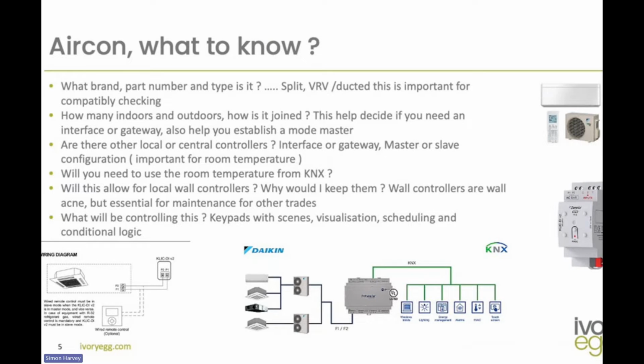To give you a description of what a mode master is: from one condenser, the condenser produces heating or cooling that pumps to the indoor units. The condenser can't be in heating and cooling at the same time - it can only be in one. With one condenser and multiple indoor units connected to it, you will have a mode master, and that mode master decides whether the condenser is producing heating or cooling. What we have to do then is ensure all the other indoor units are set up as slaves.